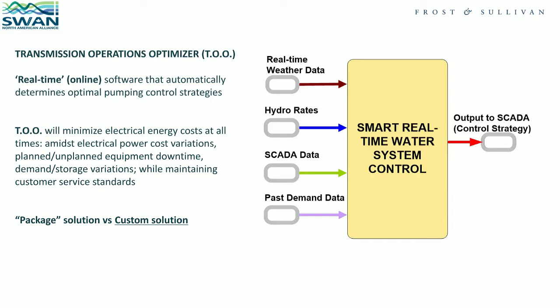Another input is SCADA data, so it looks at system pressures, flows, equipment availability, pump characteristics, capacities, pump curves, all of that. It also takes in past demand data - consumption and historical data.